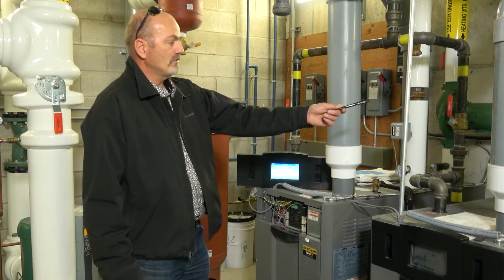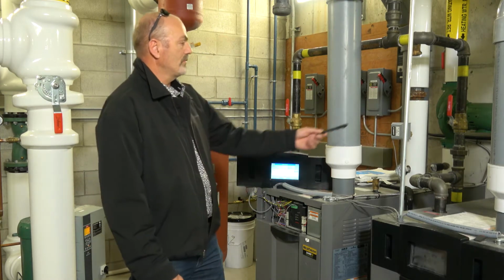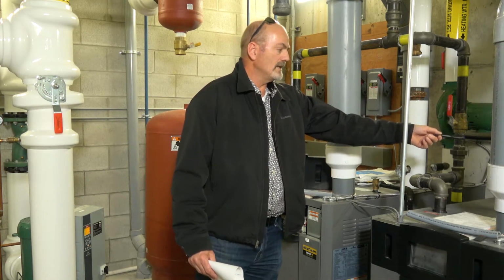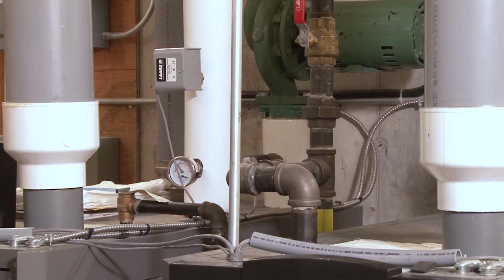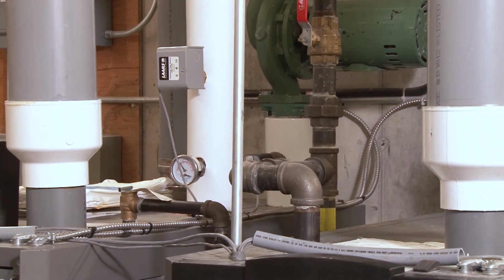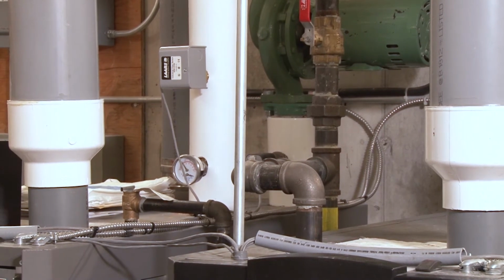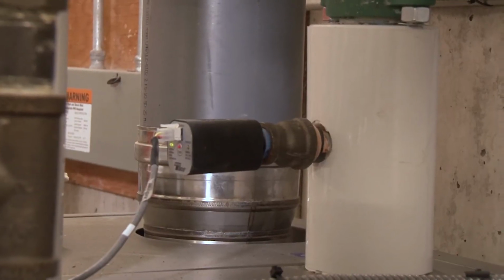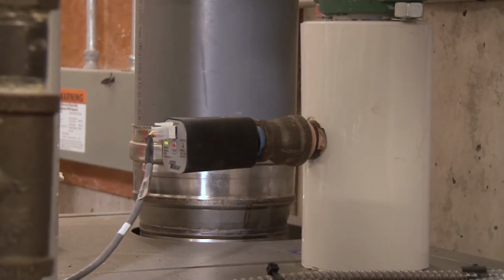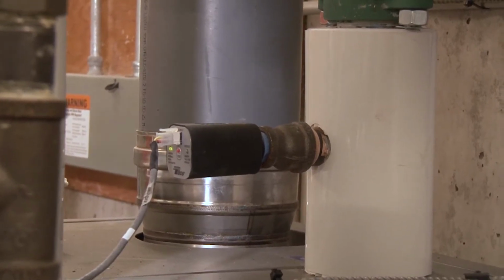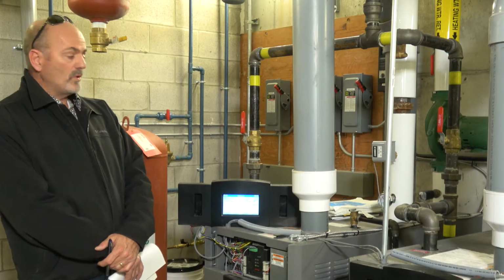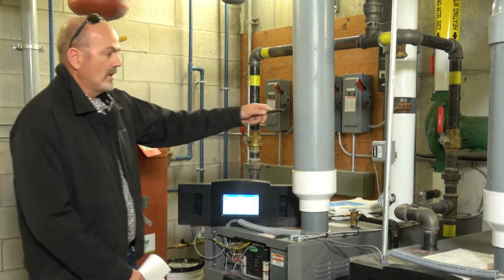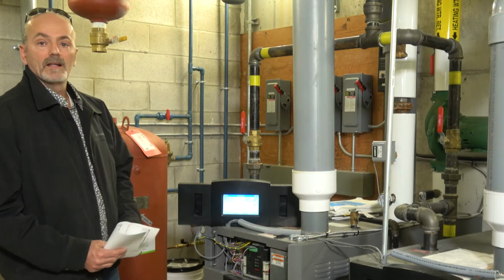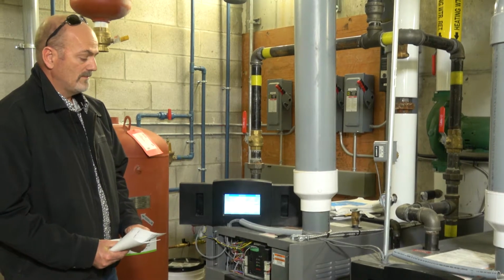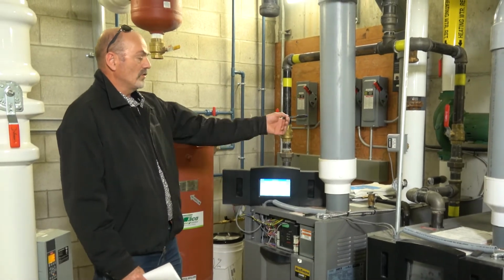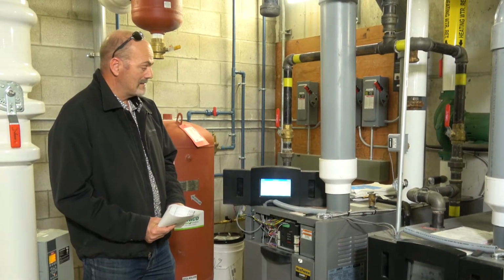In addition to that flow switch, there's a secondary safety control, a little further over below the pump, called a probe low water cutoff. The low water cutoff proves that we have fluid in the system and that the low water cutoff has not malfunctioned. The green light indicates that we have appropriate flow and the sensor isn't dirty, and it will allow the boiler, along with the flow switch, to prove out on the control and go through an ignition process. This boiler is currently running as both those controls are satisfied.